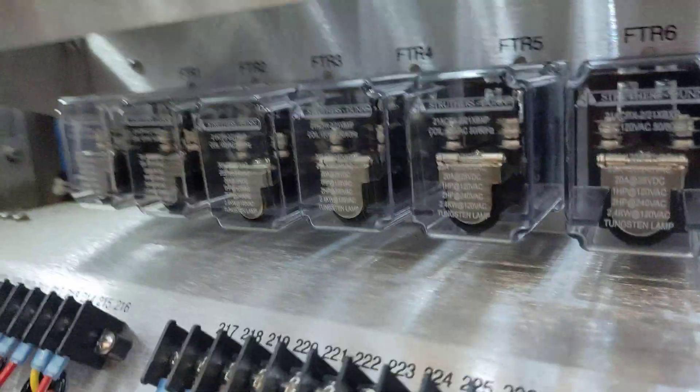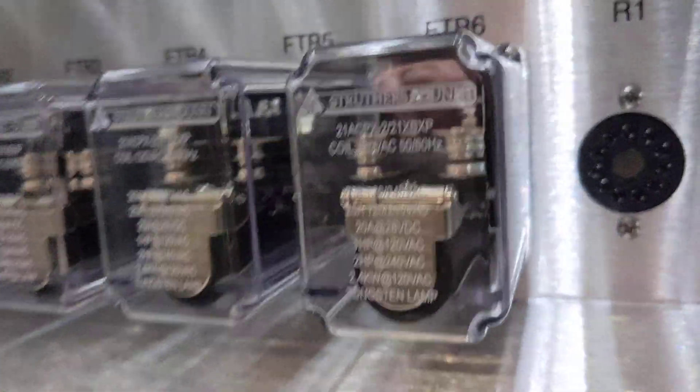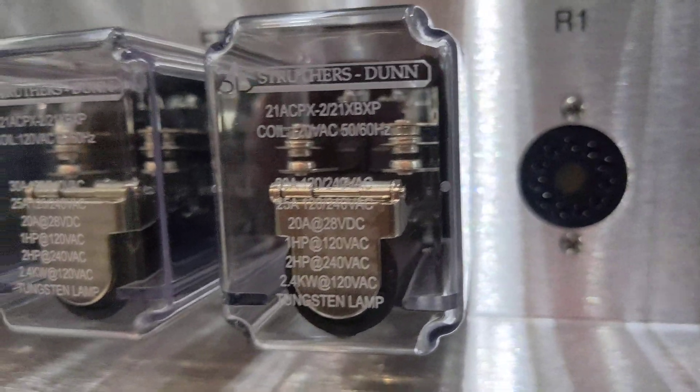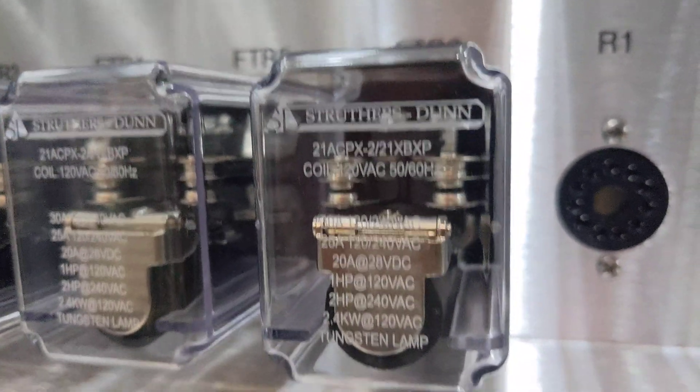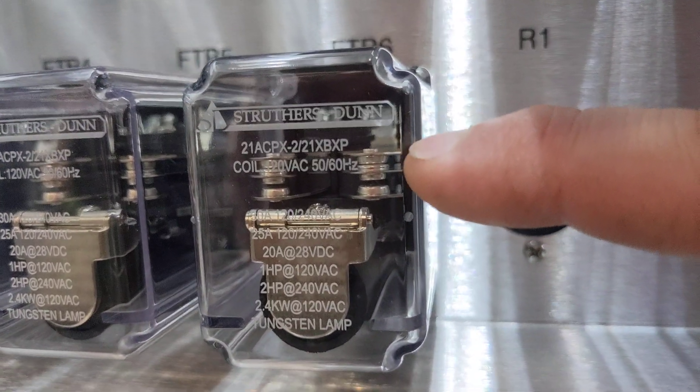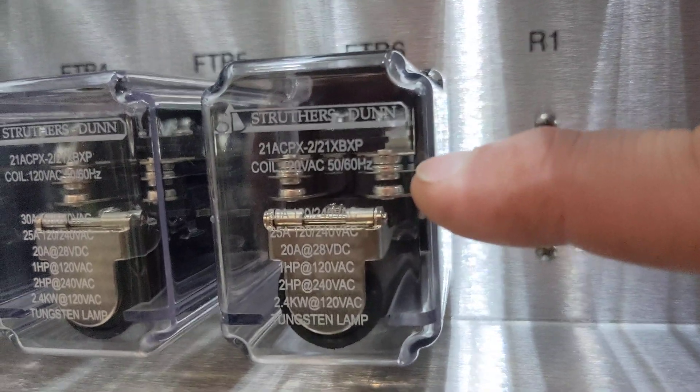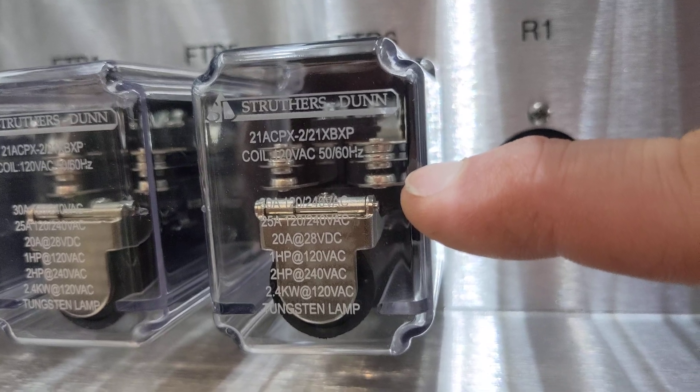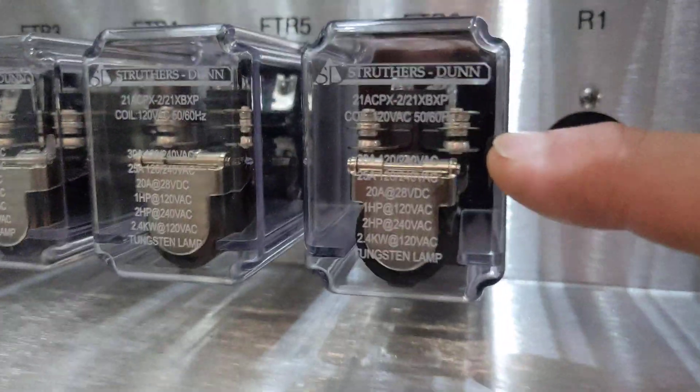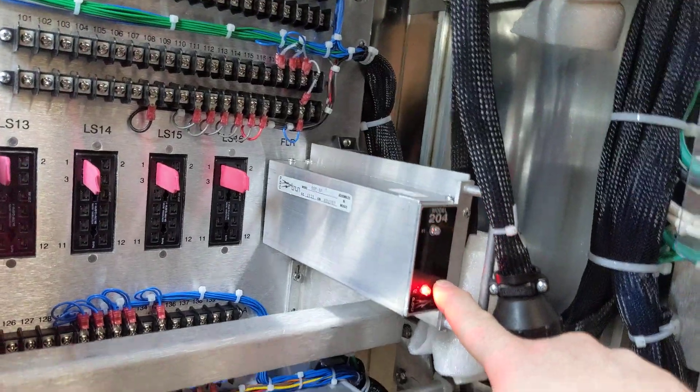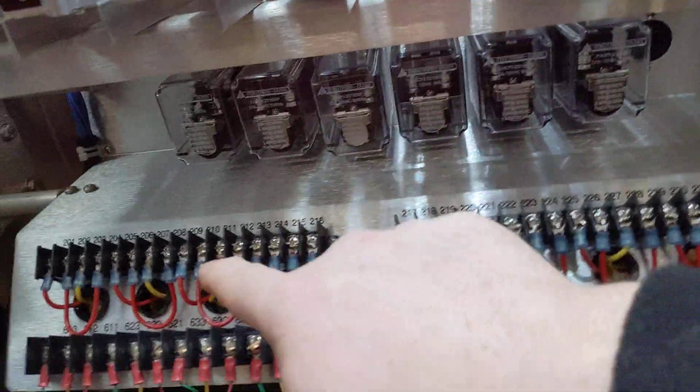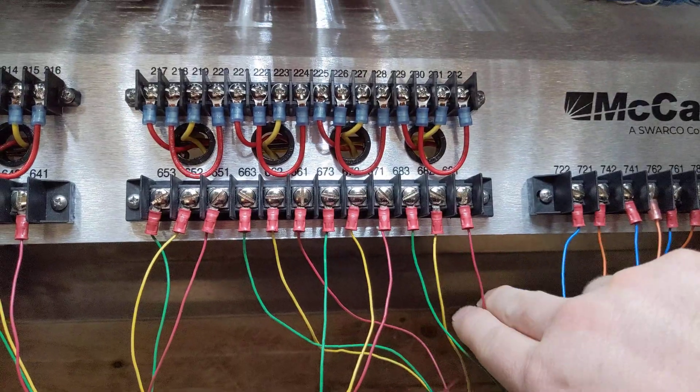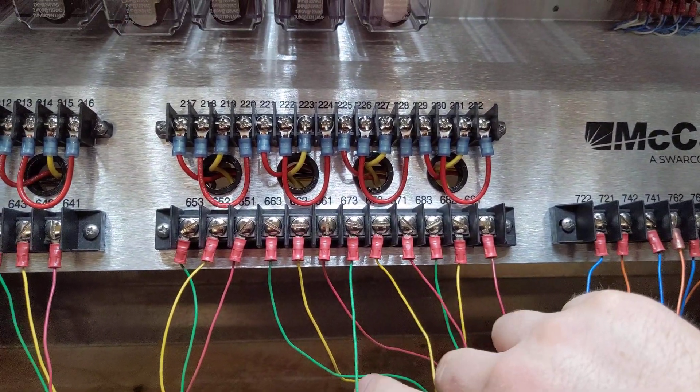So now, these are what's called flash transfer relays. And if you take a look here, really close, I got nice and close on the flash transfer relays. If you can see that right now, they're in contact with this side of the relay on the top part. There's a middle part here that if it switches down here, it's actually going to switch the circuit from these load switches that are driving the field indications. If it switches down here, it's going to be running on this guy.